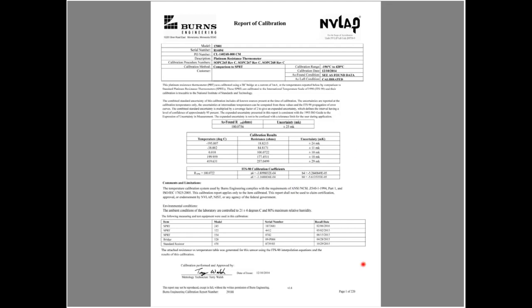Then down the bottom of the form, it'll list the equipment used and who did the calibration. A lot of these will have, in addition to this, a resistance versus temperature table that some manufacturers publish. It could be in 1 degree C increments, or I've even seen them in 1/10 degree increments of the temperature resistance relationship.